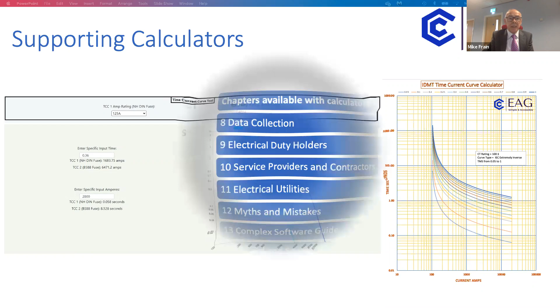And we've also got supporting calculators for time current curves on the left-hand side. They're all the range of fuses for either BS88 or NH-DIN fuses. You can simply enter the specific input time, or you can enter the specific input current or arcing current, and that will give you a disconnection time. And on the right-hand side, there are IEC IDMT time current curve calculators as well. So that's a quick run through those.